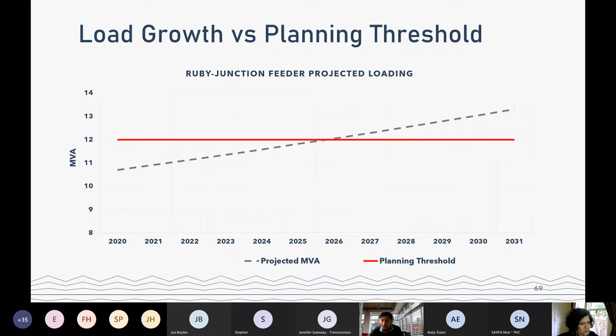So what's happening at this Ruby substation, specifically the Ruby Junction feeder and the Ruby Carline feeder? At Ruby Junction, we saw that load growth is going to exceed the planning threshold by 2026. When we did our current state analysis, we found there are no violations, so there's no issue with the feeder itself, but it's above the planning threshold, which means that if there was a failure of one component and we had to shift load, it's possible there would be issues during that emergency or contingency condition.